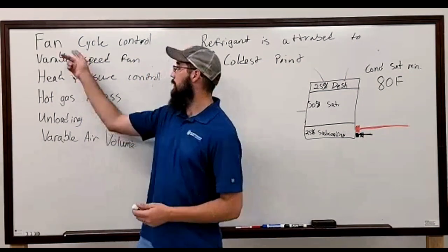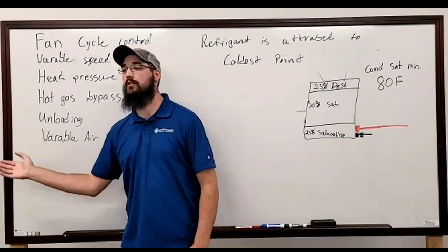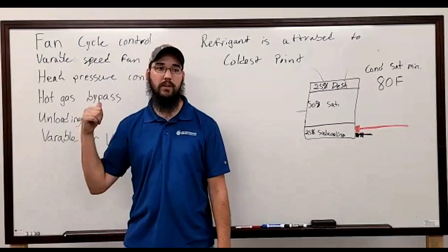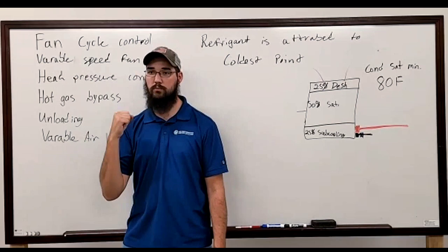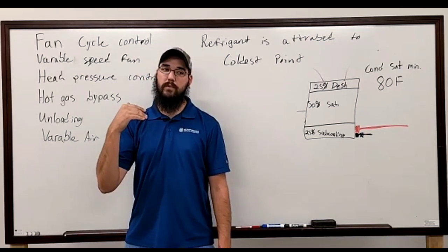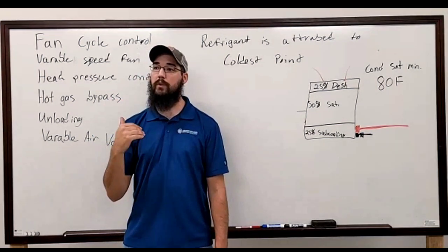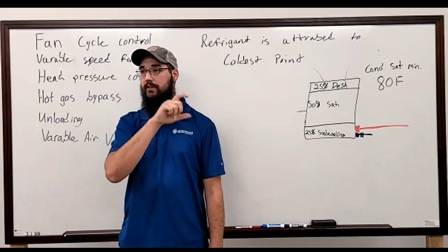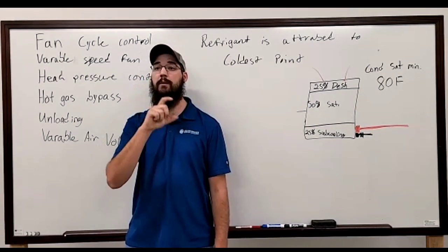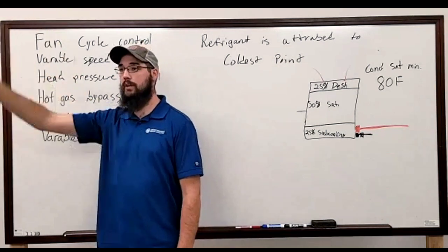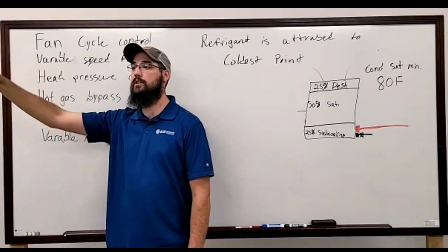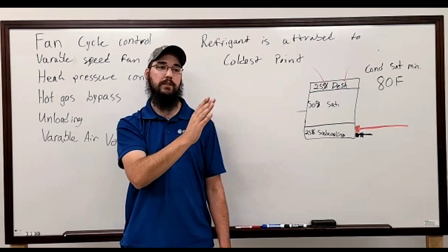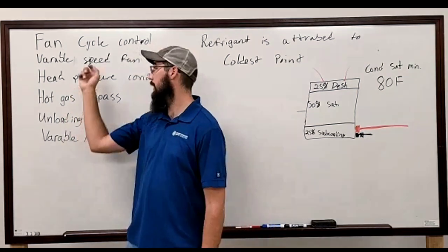But the nice part about that is the condenser is extremely taxing on the whole system, because you're talking about this nonstop swing of pressures. The compressors are constantly feeling it, the fan motors really feel it. Every time you slam one of those closed, those bearings really take a punch. Variable speed helps in that way. We can achieve tremendous efficiency out of a variable speed motor strictly because for every 2 or 3 PSI that the system shifts, we can speed up and slow down that motor fast enough to keep up with that change. To where instead of having this swinging graph, we just kind of have this barely nudging along. We really don't change much. Their goal is to achieve a specific set condenser saturation temperature at any given time, and they can accomplish that with variable speed.